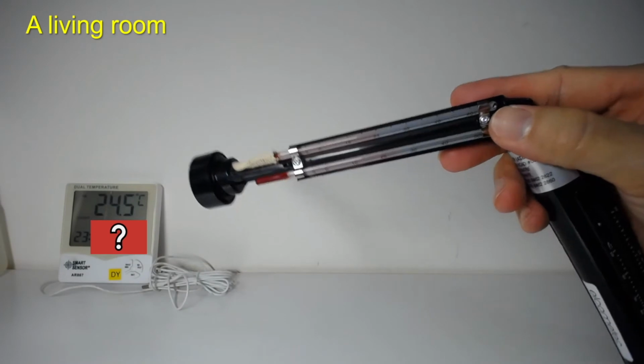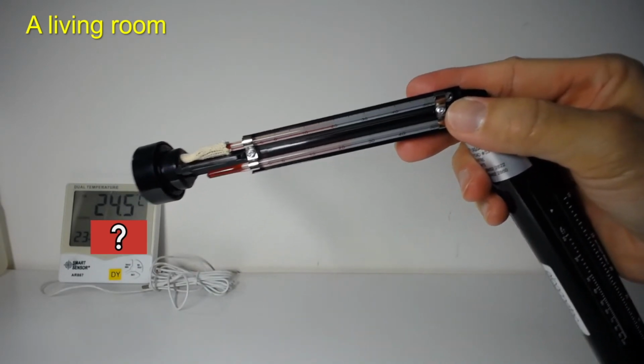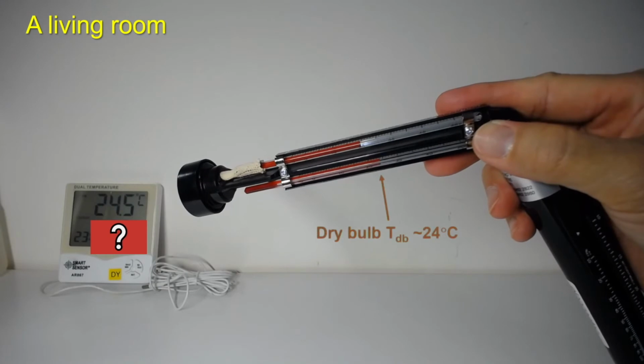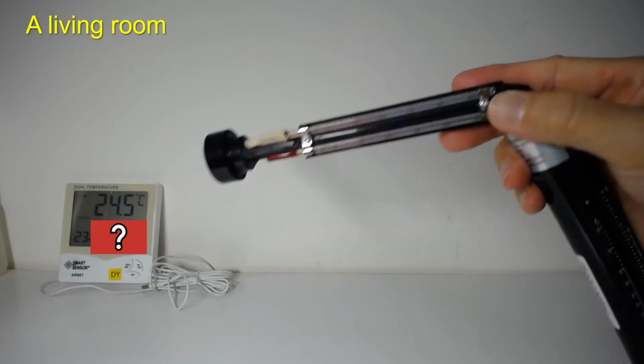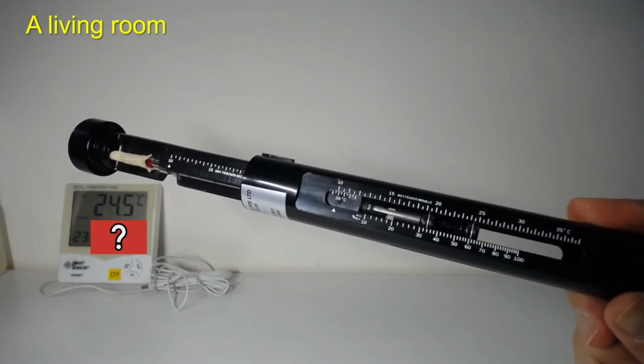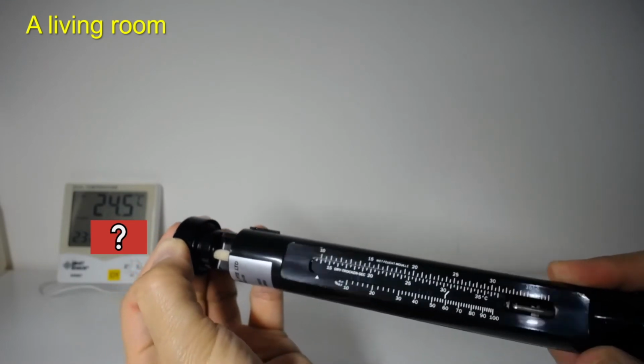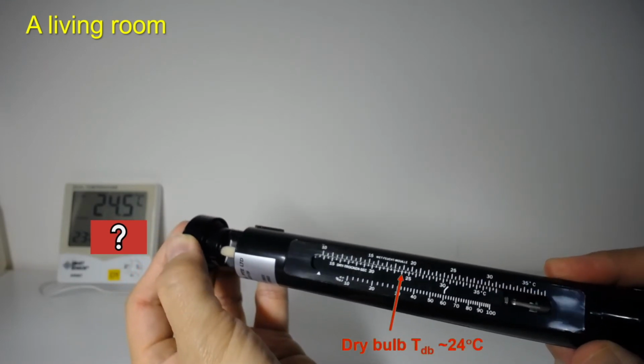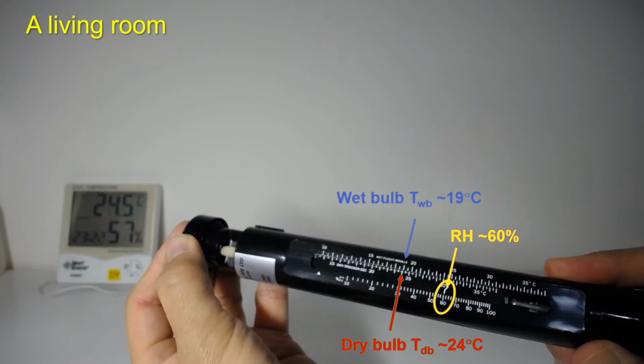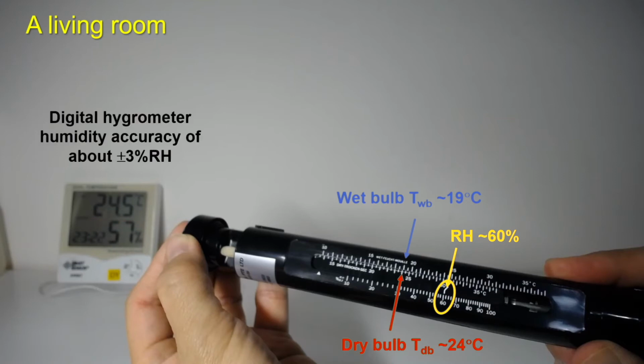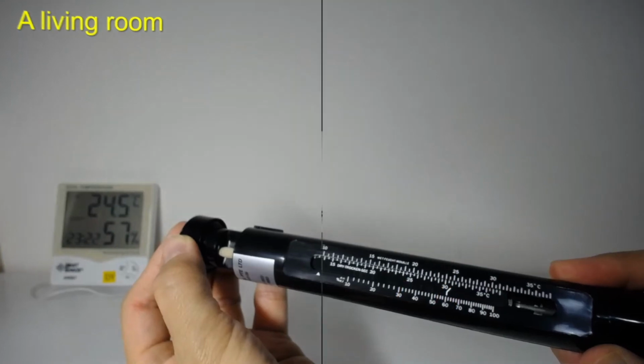We can see it here that after slinging it around for a while, the two temperatures are different. Dry bulb temperature is about 24 degrees Celsius and wet bulb temperature is about 19 degrees Celsius. The hygrometer has a convenient scale to determine the relative humidity. So we set the dry bulb temperature to 24 and the wet bulb temperature to 19 here, like this. We can then read out the relative humidity is 60%. Let us now show you the relative humidity measured by the digital hygrometer, which is 57%, and it is quite close to the measured one by the Sling hygrometer.